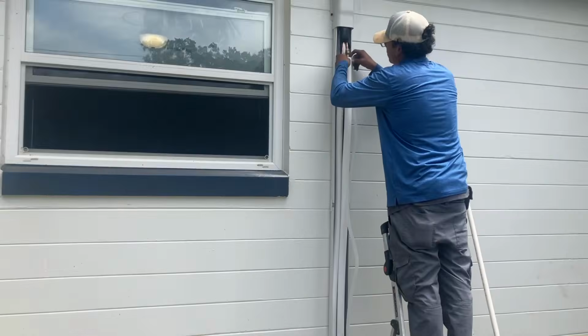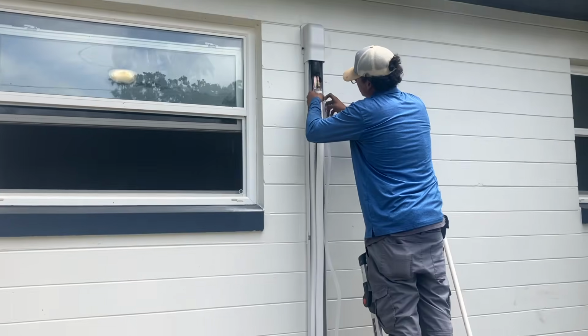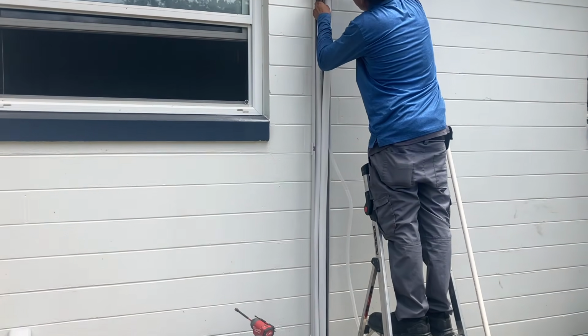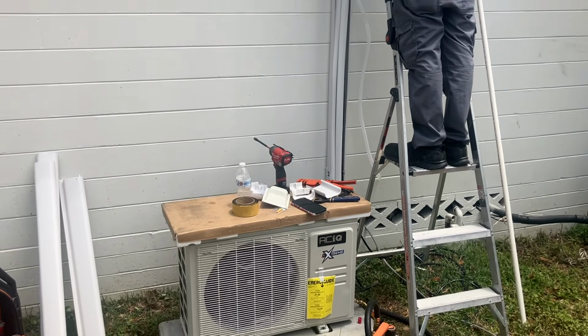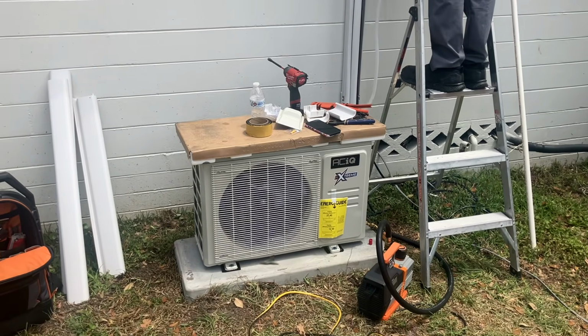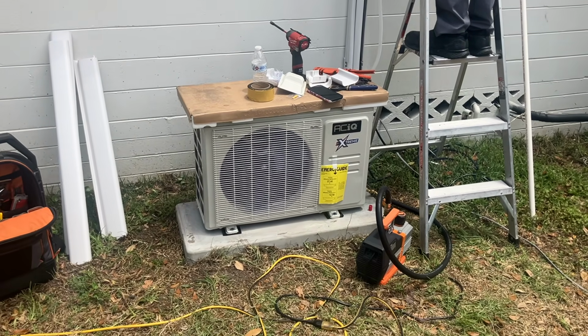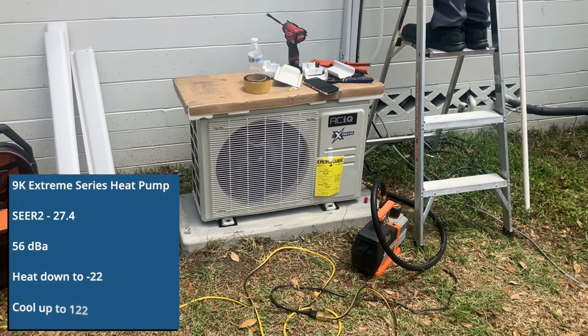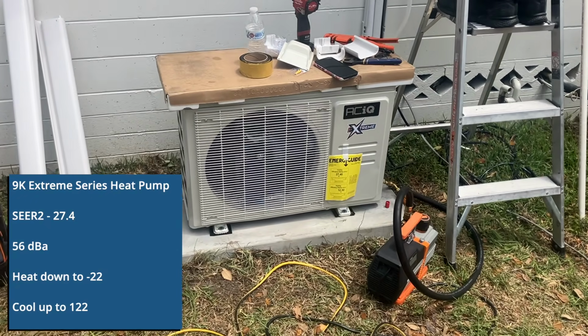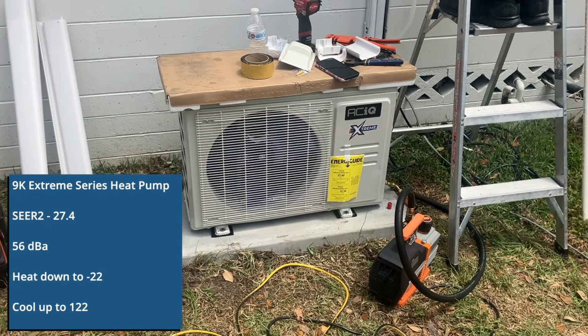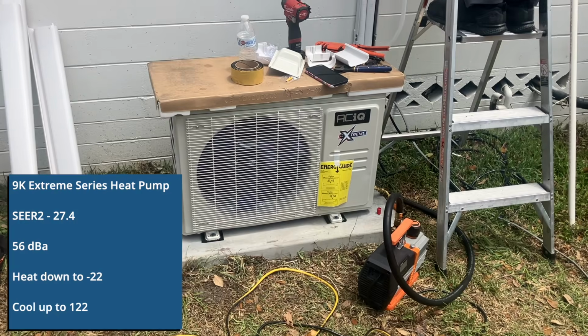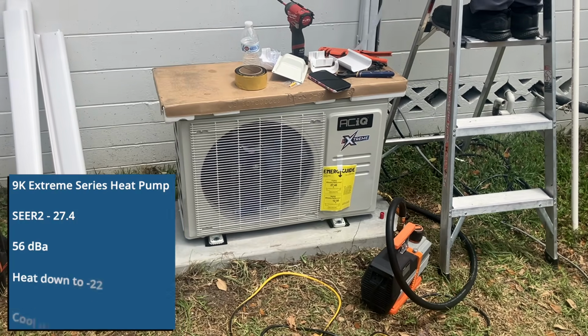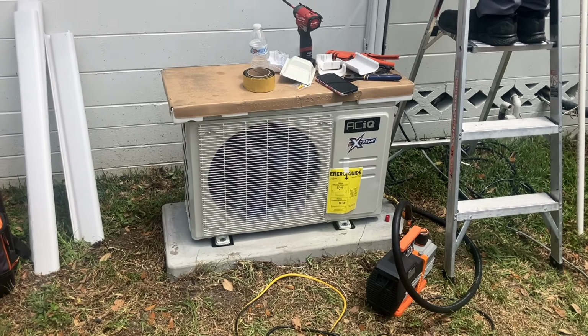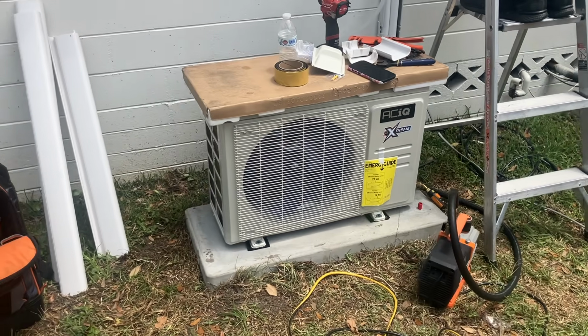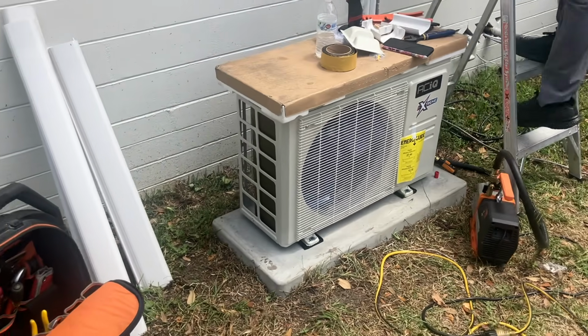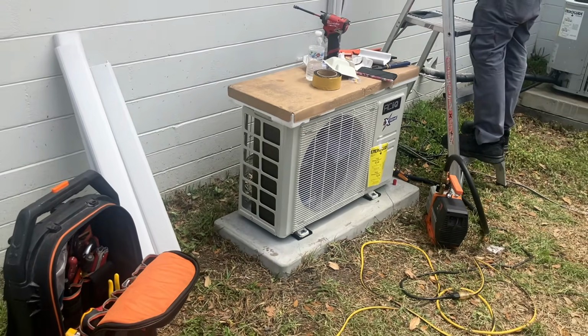Juan is finishing up the installation by running that drain hose down the inside of the line hide to the ground. You may think we're almost done, but now comes the most important part of the job, and that's commissioning this beautiful ACiQ Extreme 9,000 BTU single zone heat pump system. Anybody can hang a unit on the wall, but this is where we make sure it actually performs well for many, many, many years.